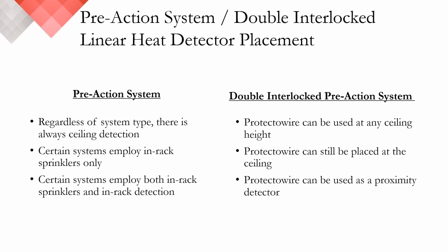Regarding detector placement, specifically linear heat detector placement, we have seen it all. In almost all cases, sprinklers and Protectowire linear heat detection are run at the ceiling level. We have also seen applications where there are only sprinklers in the racks, as well as applications where there is only Protectowire in the racks. How the racks are protected becomes both an engineering design call as well as a local AHJ decision. If you are looking to design, service, or install a system, please check with your insurance company and local authorities to determine any requirements in your area.